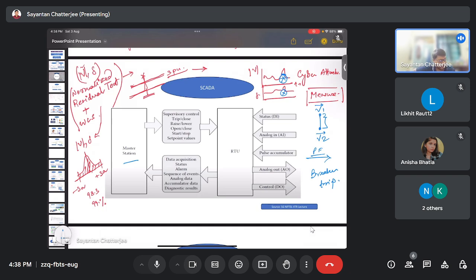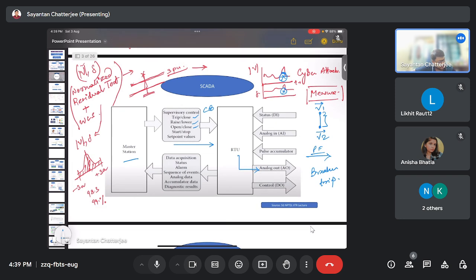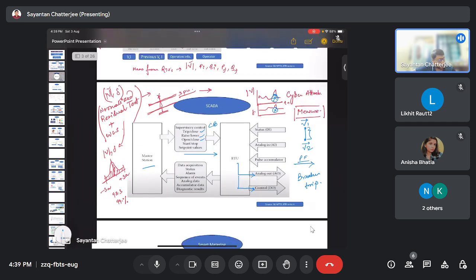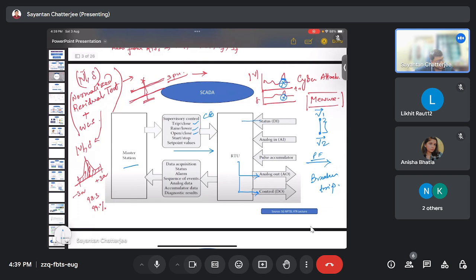So here we have the master station. We have the supervisory control actions, like trip, close, the circuit breaker status that we need to perform, whether we need to close or open, start, stop. These are the things from the master station. We deliver this information to the RTUs, and after that the RTUs deliver this information through the analog outputs. Based on the information to be transferred, the RTUs deliver it using the analog input output path. They take action so as to deliver the information from the master station, right? So that's the basic overview.